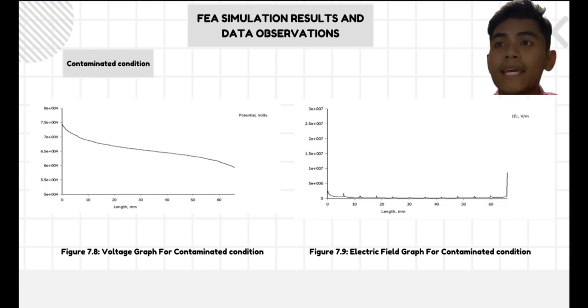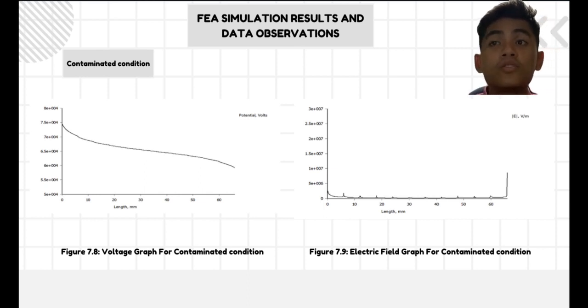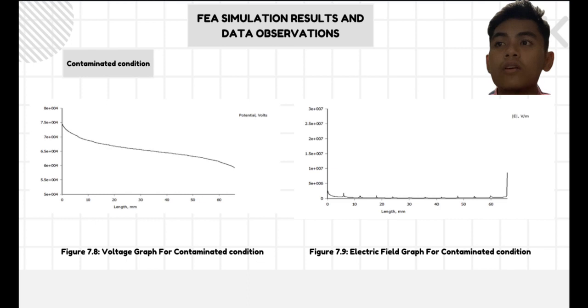In the graph, the voltage is observed to decrease slowly from 75 kV to 60 kV as the length of the insulator increases by 65 mm. This indicates that as the length of the insulator increases, the voltage withstand capability gradually diminishes. This reduction in voltage withstand capability can be attributed to the presence of conductive paths formed by contaminant on the insulator surface. Okay, figure 7.9 illustrates a graph showing the relationship between electric field and length for a contaminant condition.